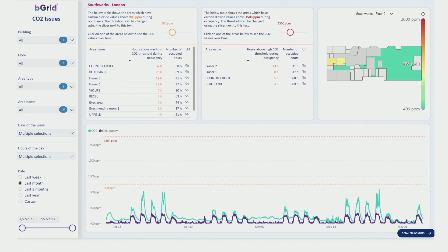Using the same dashboard, we can see there's a meeting room called Fraser 2, which had 13 hours of CO2 higher than 1500 ppm, and it's a meeting room on the ground floor - either this one or this one. Again, a confined small meeting room. So either the BMS or the HVAC doesn't react the way we want, or maybe there are more people than the space is designed for. This is how we can investigate and find out the reasons.